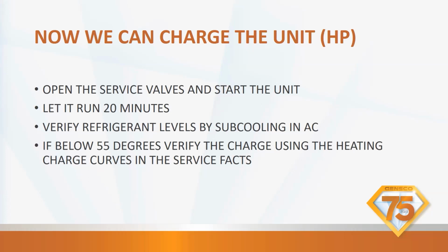So we can charge the heat pump. To charge the heat pump, after we've gotten everything done with our pressure test and our evacuation, then we're going to open the service valves. We're going to start the unit. Again, we need to let it run for 20 minutes before we get our charge finalized, right?